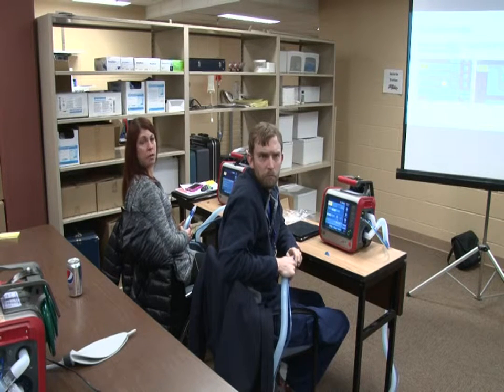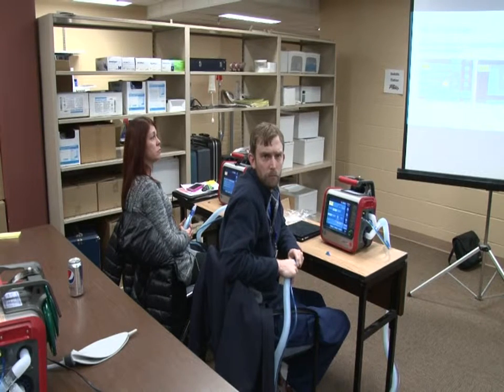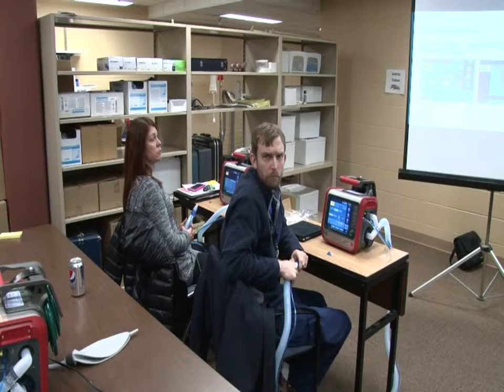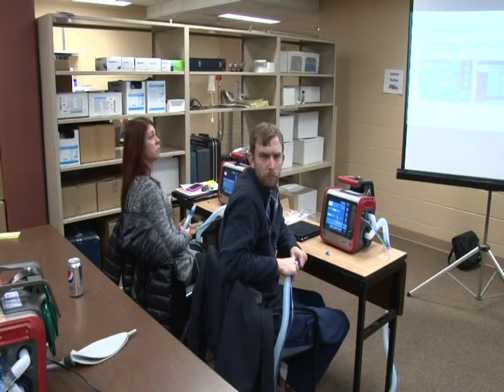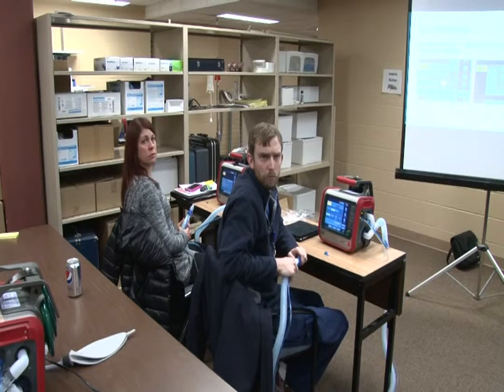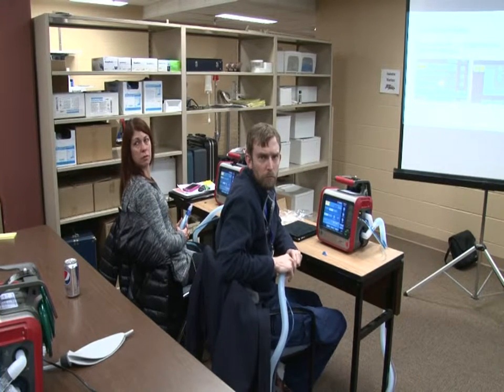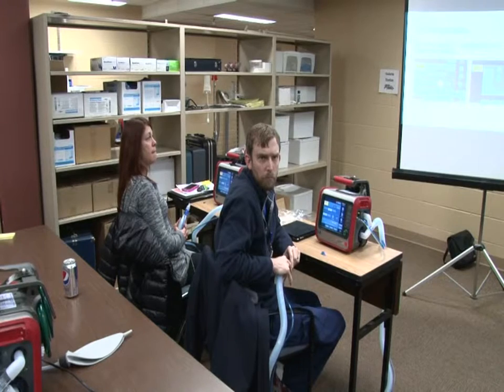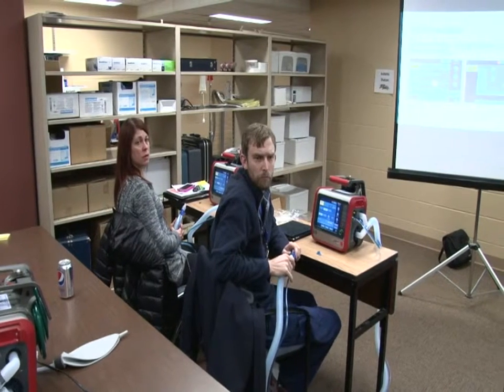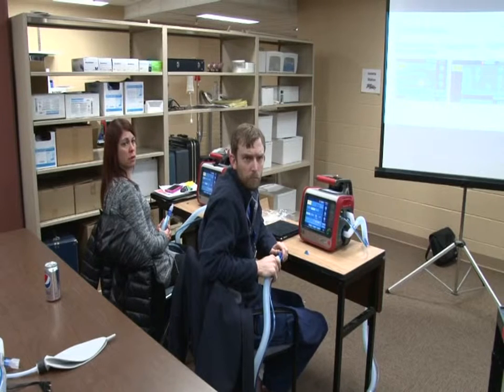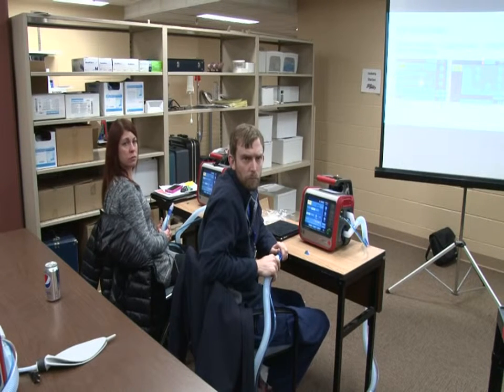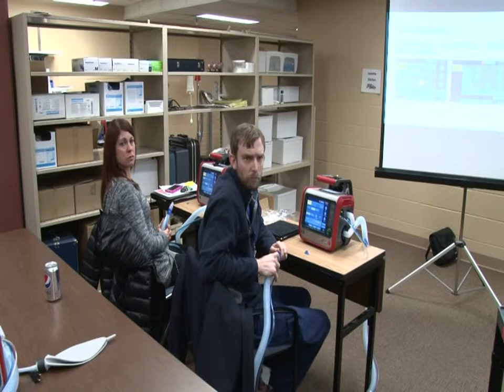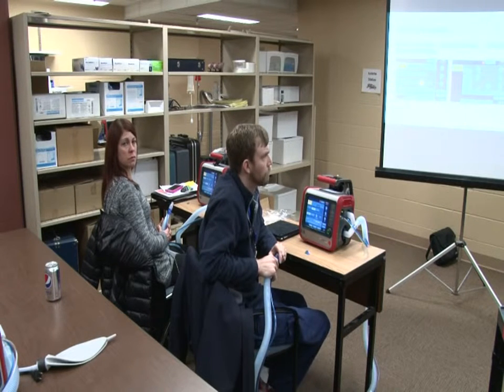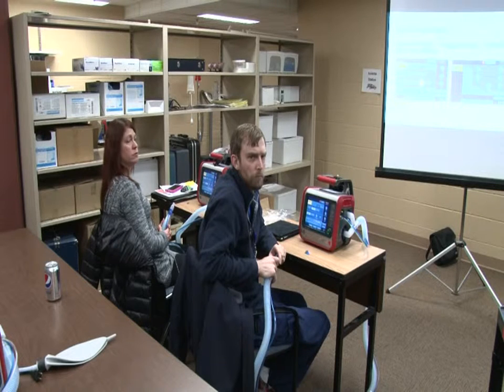The issue has come up though that you've technically taken something that's sterile out of the bag and you potentially contaminated it, so you could do any or all of those things. It's not really a fill question, it's more of a policy about how you want to do it. If you get these coaxial circuits, they have that little blue cap, so what I would do in that case is do the flow sensor calibration first, and then when you go to do the tightness test, take that little blue cap and put it on, and when it's done, don't uncork it anymore, and you're good to go then.